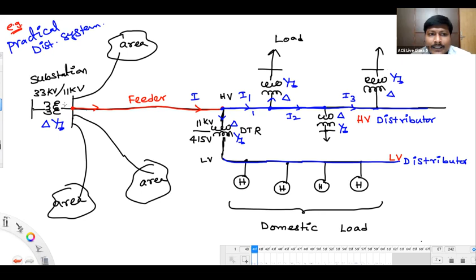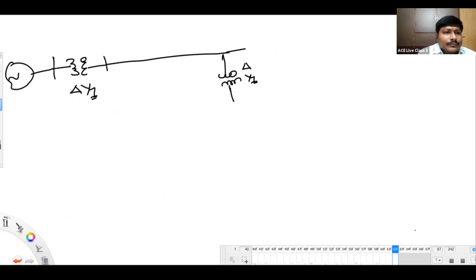And another doubt, sir. Listen. This is a delta star ground, your substation transformer. This is your delta star ground distribution transformer. So it is some source supply. Now say you have a fault on this feeder at some place. Do you have any circulation of zero sequence current in this case? Maybe not, sir, because it is star grounded.